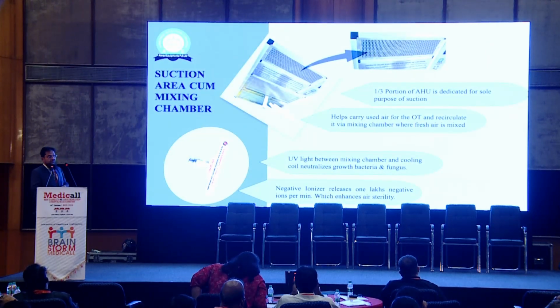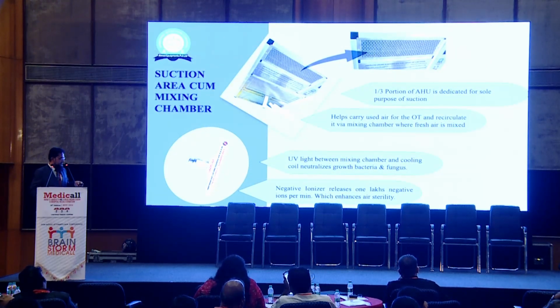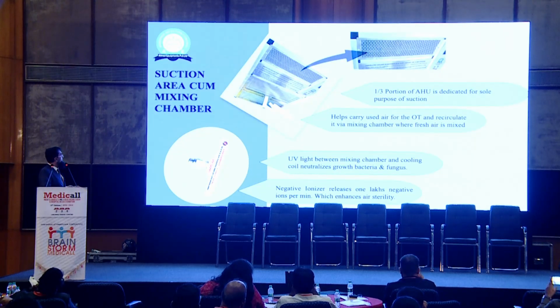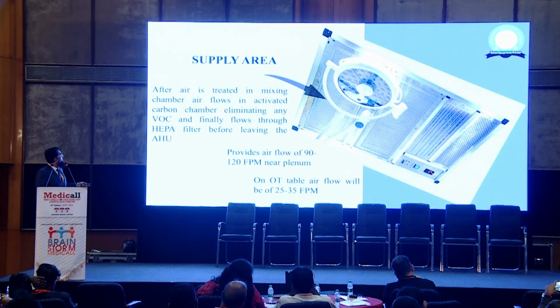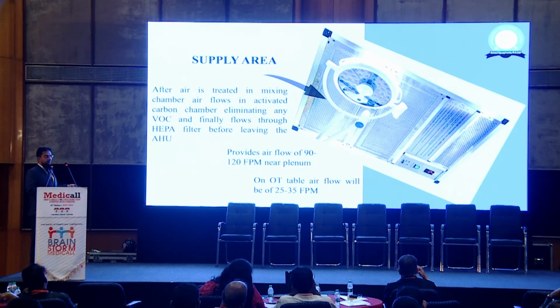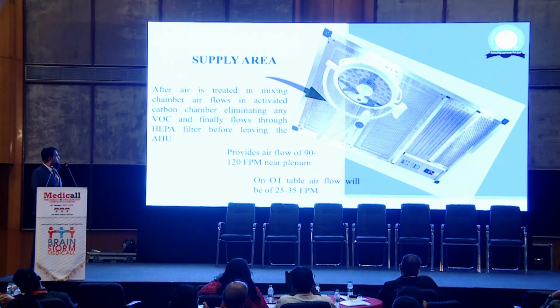See, as I told you, the first one-third area of the AHU is the mixing chamber. Then we have given the negative ionizers and the UV light in this. Then the face damper is also coming in this area. This is the supply area where the HEPA filter and activated carbon filter are given, which will maintain the 90 to 120 FPM flow on a grill level, and on the table level it will be around 25 to 35 FPM.